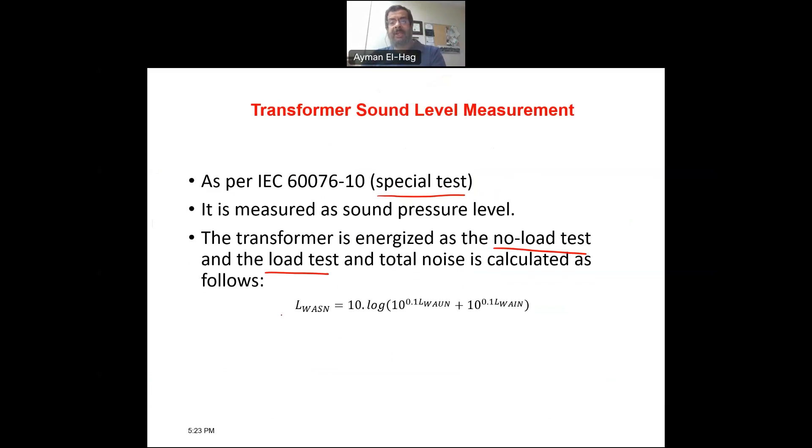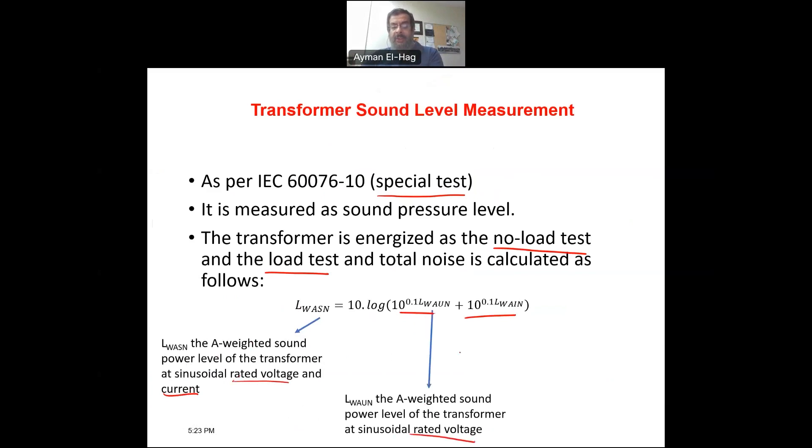So the summation of these two factors is basically the weighted sound power level due to the rated voltage and current. This component is due to the rated voltage and this component is due to the rated current. So you do the test twice, add them using this formula, and then this is the estimated level of noise from the transformer coming from both the voltage and the current.